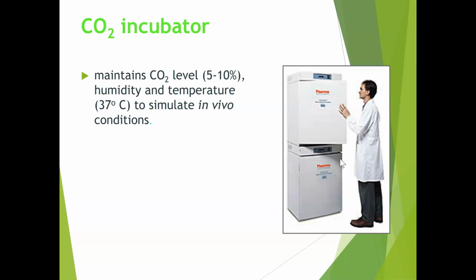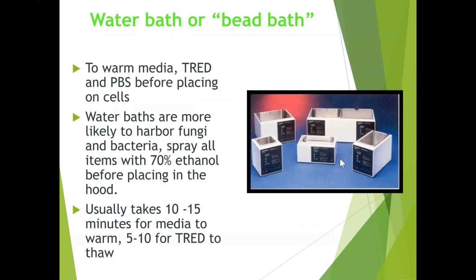CO2 incubators must be kept meticulously clean so as to avoid contaminating the cell lines growing within them. Should a culture become contaminated, a decontamination protocol should be employed before continued use growing more cells. A water bath or a dry bead bath will be used to warm media to the proper temperature, usually 37 degrees, before it's added to the cells. Again, this prevents cells from being shocked and damaged by extreme temperatures during laboratory manipulations.